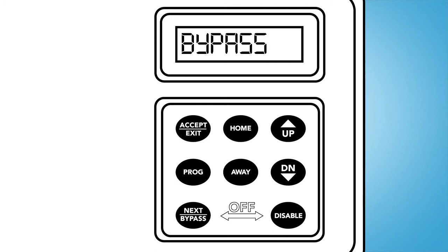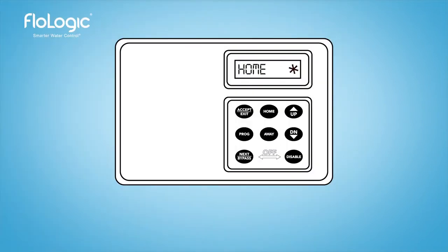To disable the system's flow monitoring, press the disable button followed by the accept exit button. When water is flowing at or above the flow sensitivity level, also called the drip rate, you will see a pinwheel graphic rotating on the screen indicating a flow event is being monitored. When the flow stops, the pinwheel disappears and the timer resets.